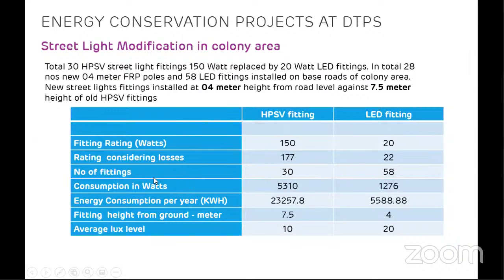Again, similarly, we calculated losses, number of fittings and consumption, and finally we got the same average lux level. Actually, the lux level improved from 10 to 20. Now here it is street light, so the lux level is not 100 or 150 like your living room. The lux level required for street light is much lower because you don't have to carry out any detailed or precise activities, just general illumination. So the lux level, which was earlier 10, is now increased to 20. And the energy consumption is reduced from 23,000 to 5,500 only.